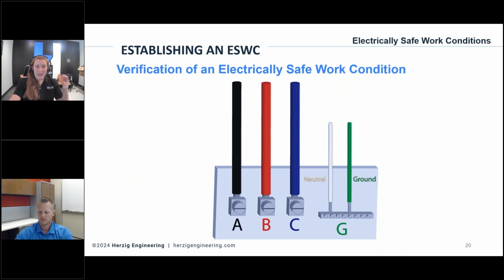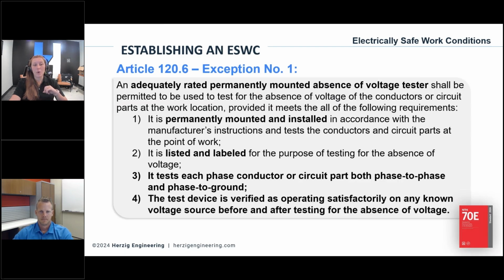Okay, so that's step number 7, live, dead, live, phase to phase and phase to ground with a meter. There is an exception if you have an adequately rated permanently mounted absence of voltage tester. It does have to be permanently mounted and installed properly, per the manufacturer's requirements, and connected to all the circuit parts that need to be tested. It's listed and labeled for that purpose, and it will do the same thing that you would have done by hand. In other words, it will test each phase conductor or circuit part, both phase to phase and phase to ground, and has its own ability to do the live, dead, live portion of that. So it has something to test itself to make sure it's still functioning.